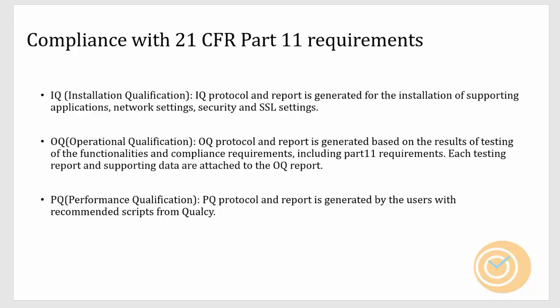Make sure you have IQ protocols and reports when you are installing the software applications on the cloud servers. Make sure that you have a good protocol to define the network requirements and the supporting applications that need to be installed as part of your IQ. And also, you can define the SSLs or the security settings that you would need for the cloud server to work properly.